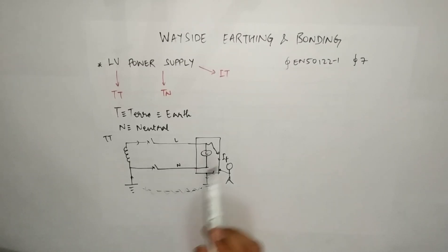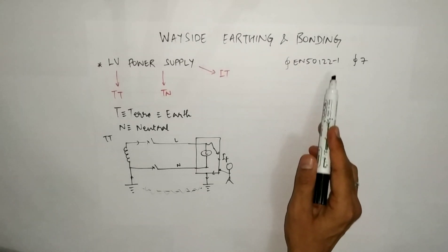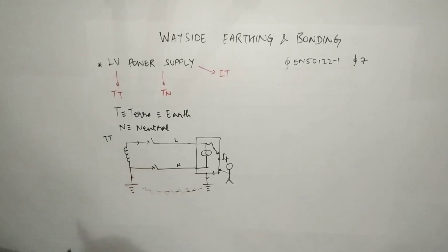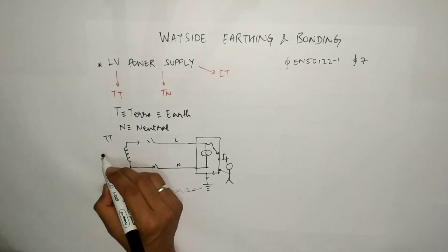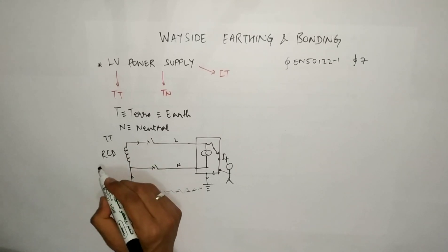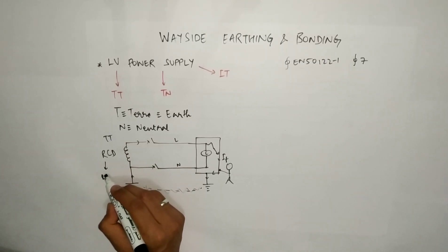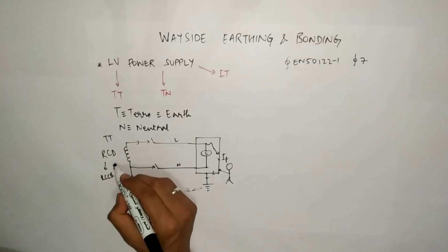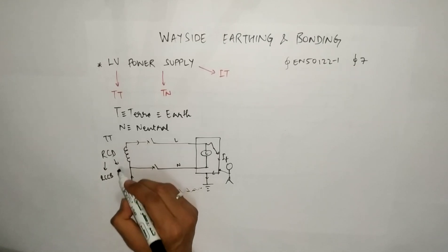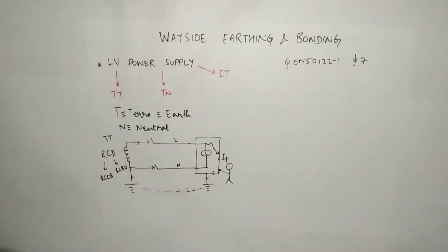To be on the safe side, EN 50122-1 recommends that when you go for a TT system, always use an RCD. The RCD can be either an RCCB — a residual current circuit breaker — or an RCBO, which is a combination of an MCB and RCCB.